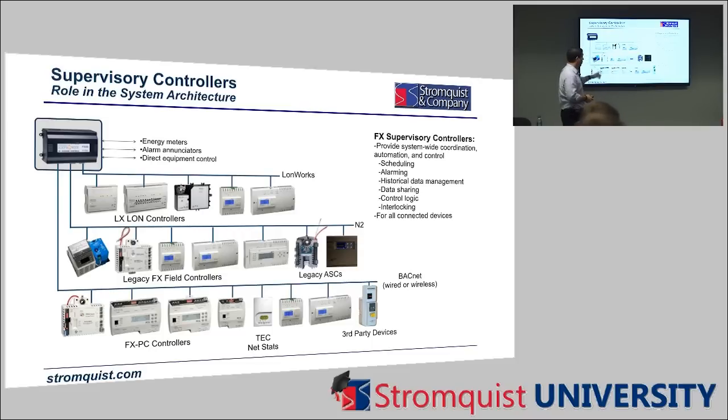So, alarming. So we talked about, to save you guys trips of running up however many flights of stairs or riding the elevator up to the 55th floor with your ladder, right? We can get an alarm. We can get that alarm sent to our smartphone, an email. It goes into an alarm portal where we have to acknowledge it to basically say, hey, I went and looked at it. This is what's going on, etc. All that's done at the Jace.